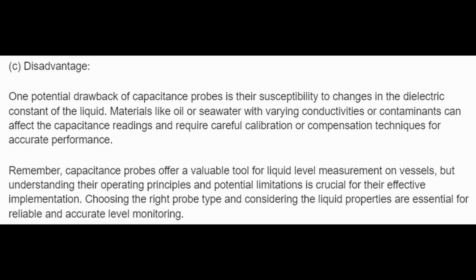Disadvantages. One potential drawback of capacitance probes is their susceptibility to changes in the dielectric constant of the liquid. Materials like oil or seawater with varying conductivities or contaminants can affect the capacitance readings and require careful calibration or compensation techniques for accurate performance. Remember, capacitance probes offer a valuable tool for liquid level measurement on vessels, but understanding their operating principles and potential limitations is crucial for their effective implementation. Choosing the right probe type and considering the liquid properties are essential for reliable and accurate level monitoring.